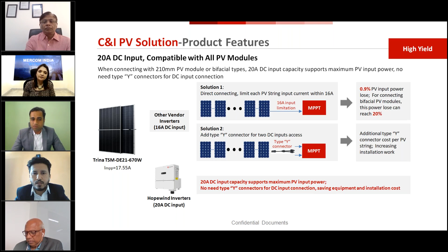So in the first case, as you can see, for various inverter manufacturers, the maximum input that you can give is 16 amperes, due to which 20% loss occurs. And in the second case, they recommend using Y connectors. In terms of Hopewind, if you are using a Hopewind inverter, this can be omitted. We don't need a Y connector because our input can handle up to 20 amperes, and we will save that extra 20%.